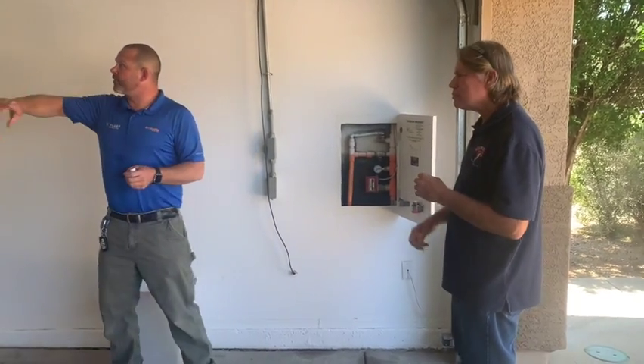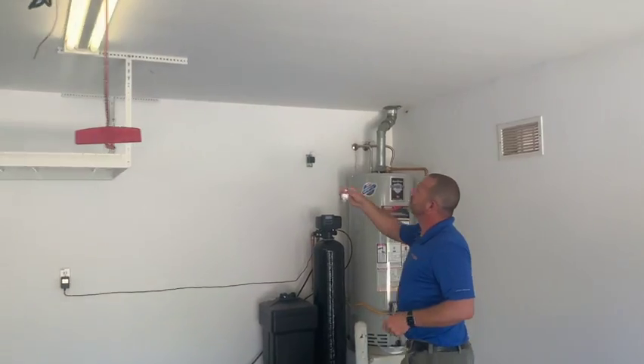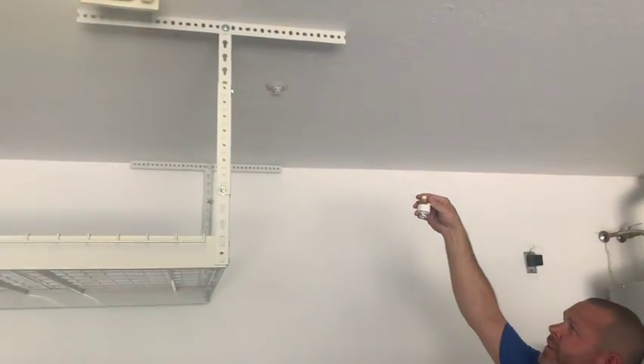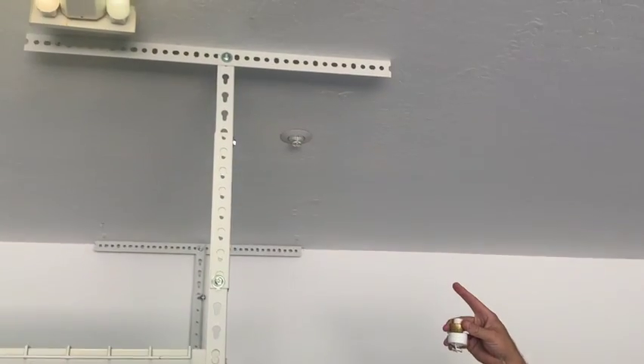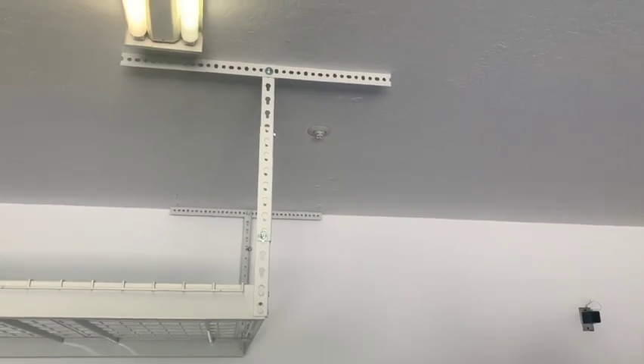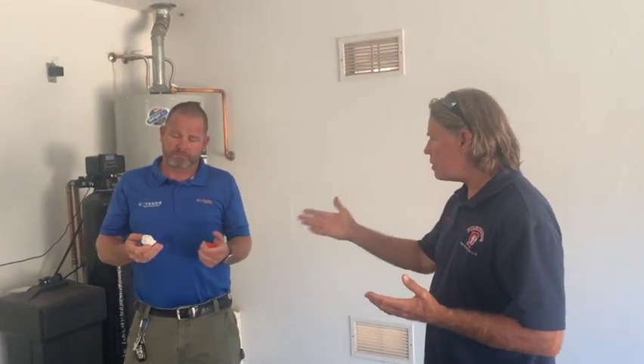Excellent. And just to give our viewers what it looks like when it's actually installed. And then as a homeowner, we can go ahead and look for any sort of water staining or anything. Right. Well, when I do an inspection, what I'm going to be looking for is painted heads. Those are not allowed by code because they compromise the sprinkler's ability to operate at the temperature that it's supposed to operate at. So you don't want any sprinkler heads that are painted. If a little bit of the trim is painted, I don't necessarily call that out because that's not a life safety issue. It might be aesthetics, and maybe they want to update that and get a new piece of trim on there. And we'll help them with that. But for the most part, we want to look for, like you said, staining, corrosion, paint, installed in the incorrect position so you don't have the coverage necessary to put out a fire, those types of things.